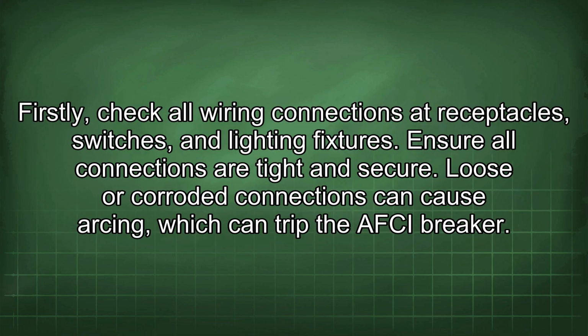Firstly, check all wiring connections at receptacles, switches, and lighting fixtures. Ensure all connections are tight and secure. Loose or corroded connections can cause arcing, which can trip the AFCI breaker.